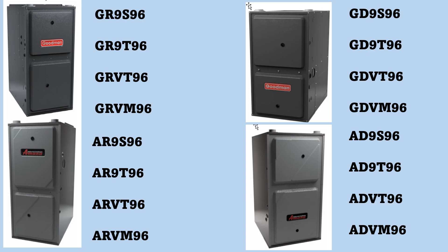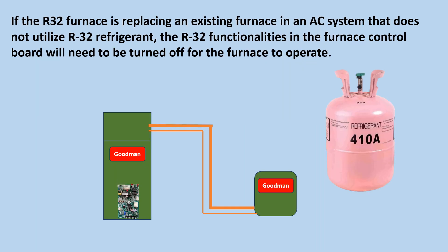All of the new Goodman and Amana R32 gas furnaces, whether from 80% to 97%, are equipped with a control board capable of shutting off the gas heat and turning on the blower fan in case of an R32 refrigerant leak in the indoor evaporator coil. If the R32 furnace is replacing an existing furnace in an AC system that does not utilize R32 refrigerant, the R32 functionalities in the furnace control board will need to be turned off for the furnace to operate.